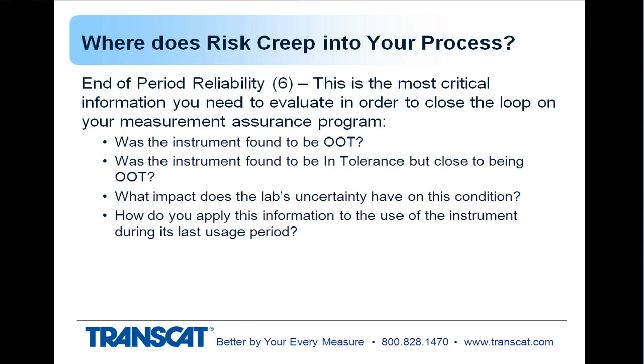End of period reliability is the most critical information you can have, because now that you've used it for that calibration interval in your process to make decisions about your product, here's the final result that tells you how it performed, how that instrument performed, whether it maintained its tolerances. Was it found to be out of tolerance, or was it in tolerance and close to the out of tolerance limit, which can still have an impact on your decisions about the quantitative values that it provided.